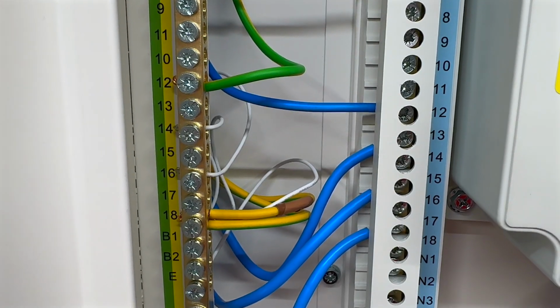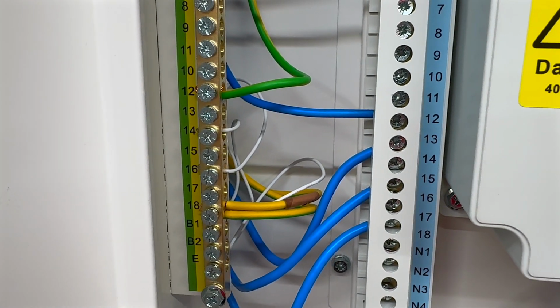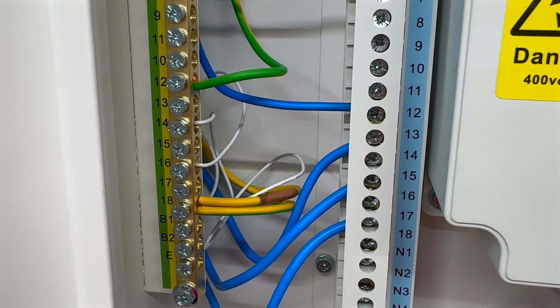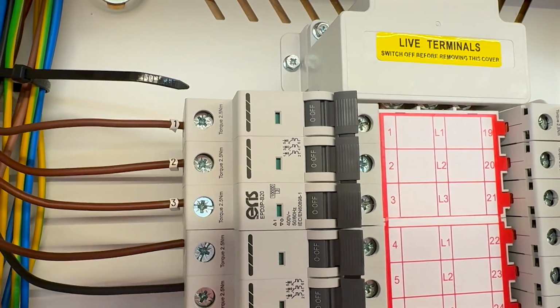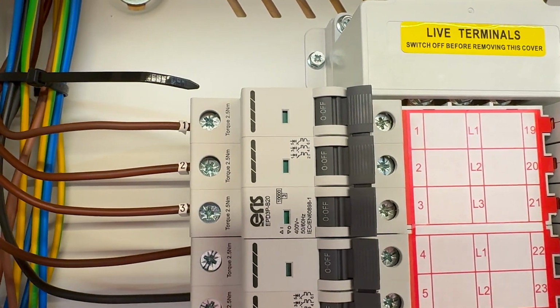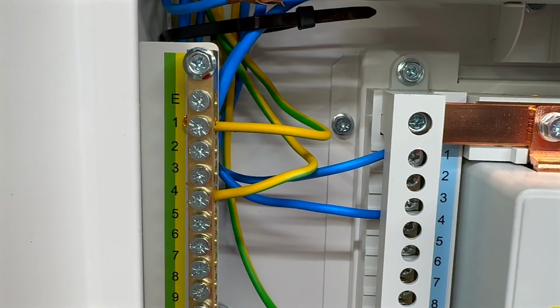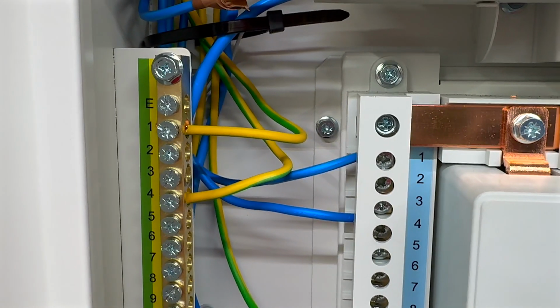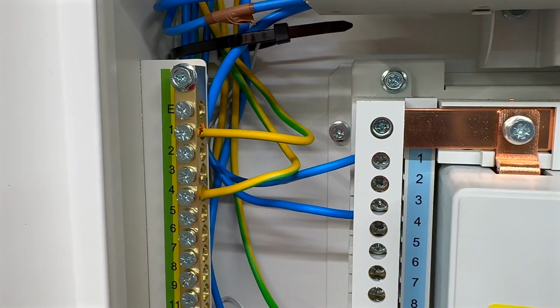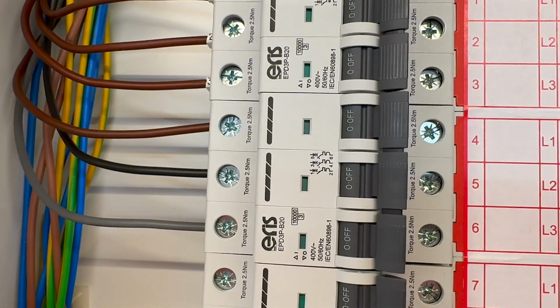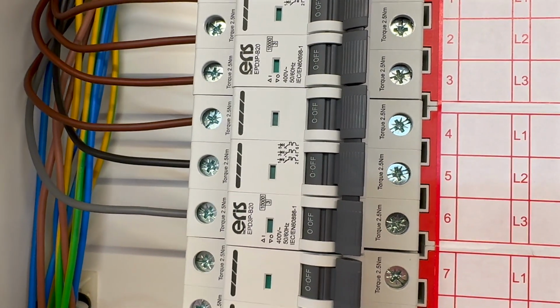For best practice, connecting the neutral and earth conductors to the terminal matching the circuit's outgoing number is recommended. For example, when connecting a 3-phase circuit to the bus bar on tabs 1, 2 and 3, the neutral and earth conductors should be connected to screw terminal 1. Similarly, for a circuit going out on tabs 4, 5 and 6, the neutral and earth conductors should be connected to screw terminal 4.